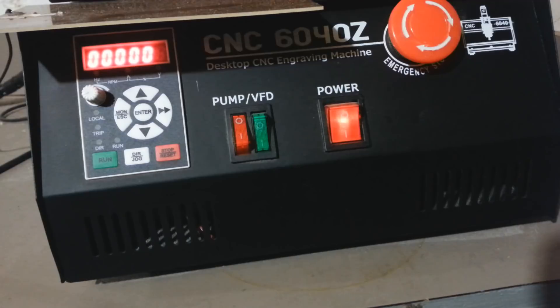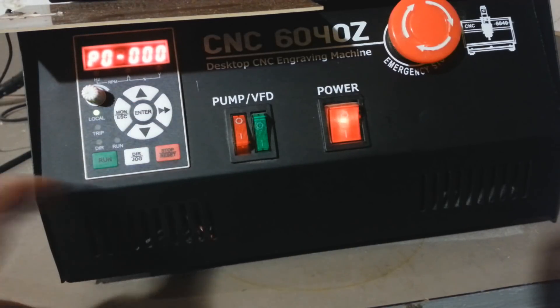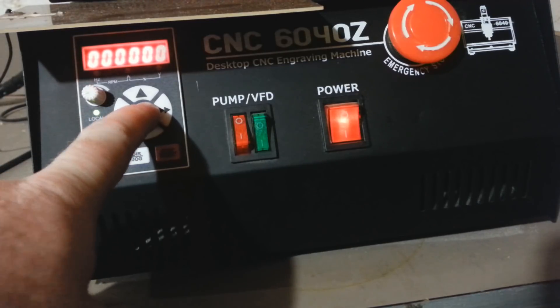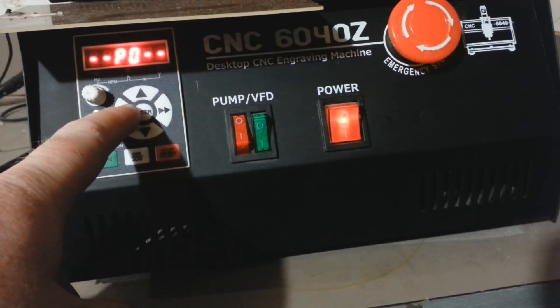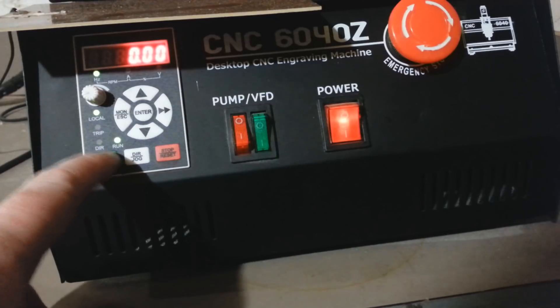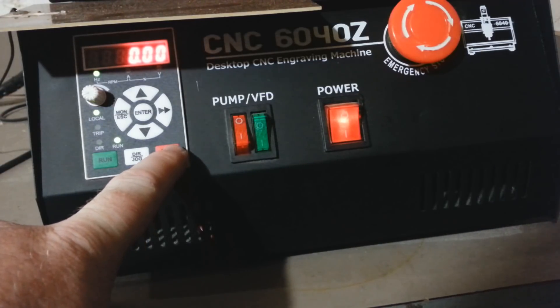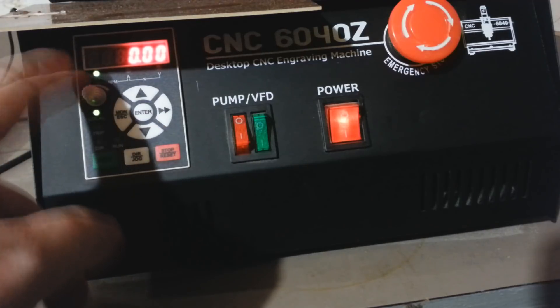We want to set P0-000 back to 0 and hit enter. Now if we hit enter to check the setting you can see it's set to 0. Press escape back to the main screen — now when I hit the run button you can see the light comes on and I can control the VFD from this panel.